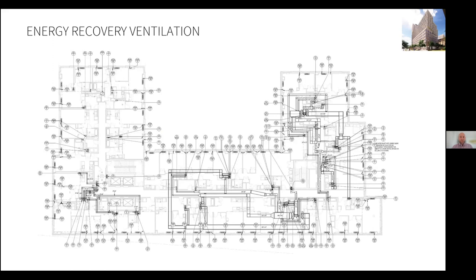That can be an issue on projects when dealing with zoning height limitations. Here you can see the mechanical plan for the 12th floor at Cooper. And on the left side, you can see the vertical risers continuing up 6 more floors to the roof in the tower portion. And then on the right, the duct offsets at that 12th floor ceiling, combining and joining before they penetrate the roof to the equipment directly above.